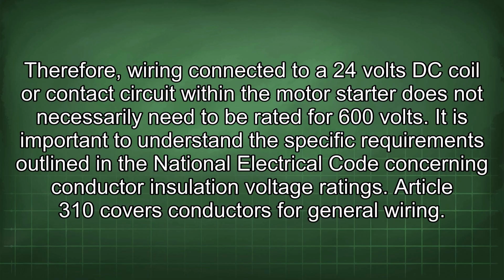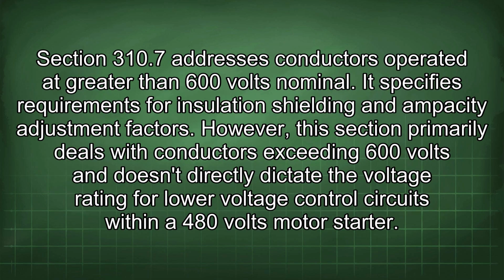It is important to understand the specific requirements outlined in the National Electrical Code concerning conductor insulation voltage ratings. Article 310 covers conductors for general wiring. Section 310.7 addresses conductors operated at greater than 600 volts nominal. It specifies requirements for insulation shielding and ampacity adjustment factors. However, this section primarily deals with conductors exceeding 600 volts and doesn't directly dictate the voltage rating for lower voltage control circuits within a 480 volt motor starter.